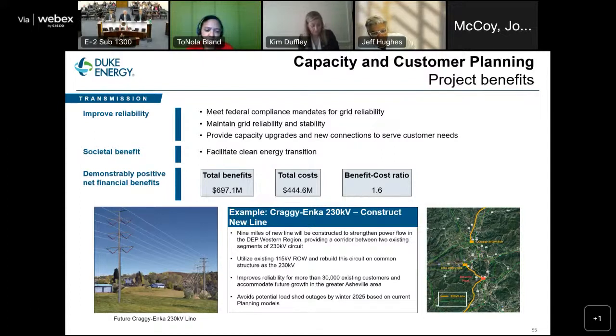Our planning models have identified a potential load shed outage scenario by the winter of 2025, based on limited ability to move bulk amounts of power between the system. So we're building a 230 kV connector line between these two points, doing it in as least impactful way as possible. We're using an existing 115 kV right of way that spans between these two stations. You can see an artist rendering in the lower left of the picture, where we're actually going to be putting the existing 115 kV circuit rebuilt on one side of the structures, and the new 230 kV line on the other side of the structures.